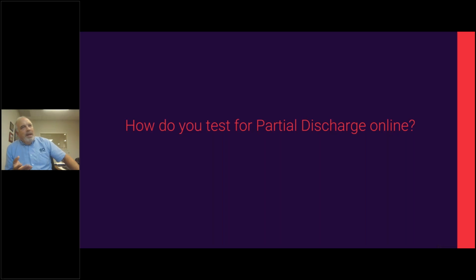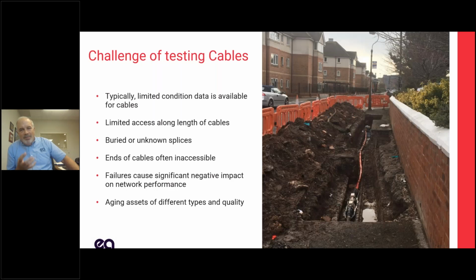So if we can't undo the past, we've got these cables that are out there, what can we do? Well, we can do partial discharge testing. It's a great way for testing a cable. You know, testing cables is challenging because most of the cable isn't accessible. They're buried. They're hidden underground. So what do we do?